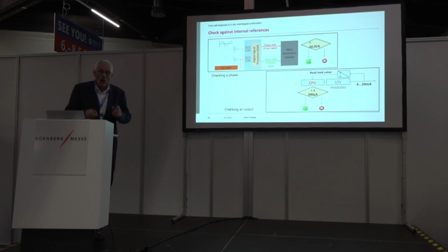This is already available in products from many companies, including Endress+Hauser, and their name is Heartbeat. They are even able to produce a verification report, a certificate, which is put out of the device via the digital interface which I just described before. That means you get this certificate. It's not a calibration certificate, it's a certificate that a verification of the important components is okay. And now I want to show you how this leads to a longer calibration period.